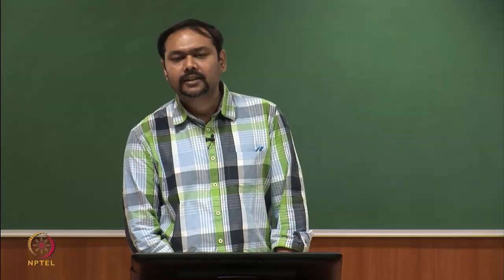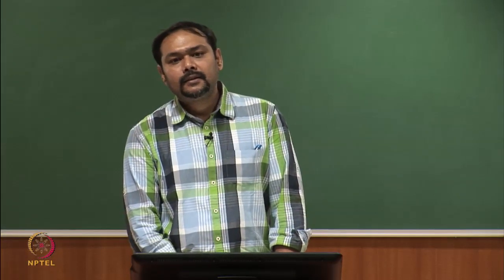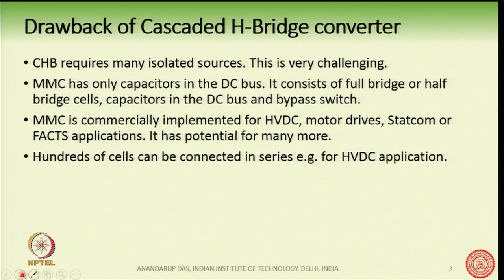MMC has only capacitors in the DC bus. The cell structure consists of either half-bridge or full-bridge. Like the CHB, it also has a bypass switch — if one cell is faulty, it is possible to bypass it and still run the converter without shutting it down. The fault-tolerant feature is also present in MMC. It is commercially implemented for HVDC, motor drives, STATCOM, and other FACTS applications.